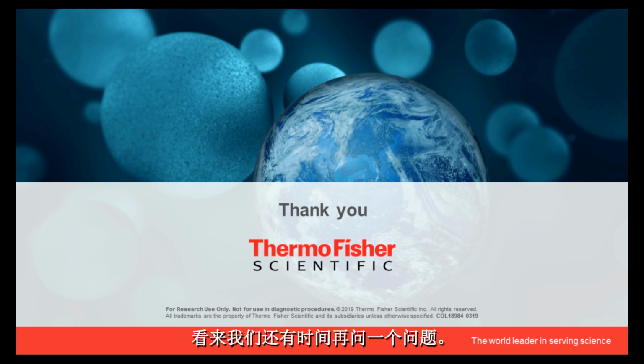Looks like we have time for one more question. How long does it take Thermo Fisher to perform their qualification services? For the life sciences instrumentation, it depends on the type of instrument, but typically between half a day and 2.5 days of on-site time with a field service engineer or application scientist, depending on the application. Yeah, and also it depends on what the customer needs, which is usually a minimum of one 24-hour test up to several days of temperature mapping to fulfill the requirements of an OQ-PQ. And that would be in the cold storage area.